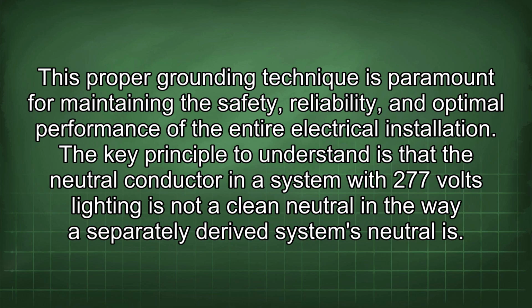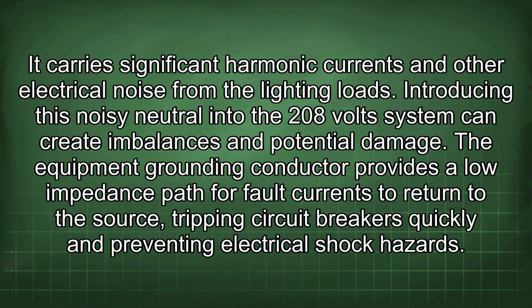The key principle to understand is that the neutral conductor in a system with 277 volts lighting is not a clean neutral in the way a separately derived system's neutral is. It carries significant harmonic currents and other electrical noise from the lighting loads. Introducing this noisy neutral into the 208 volt system can create imbalances and potential damage.